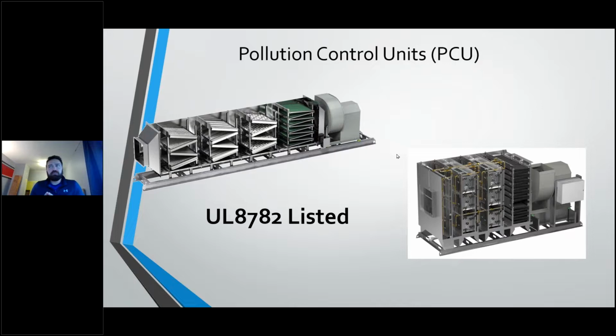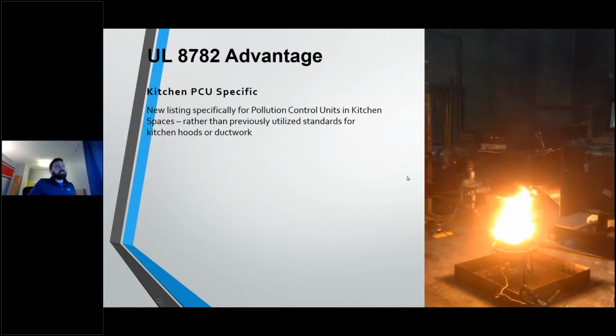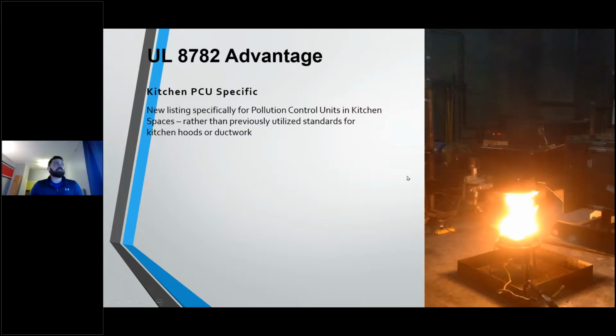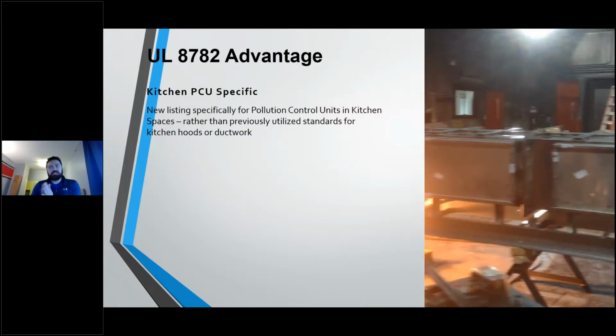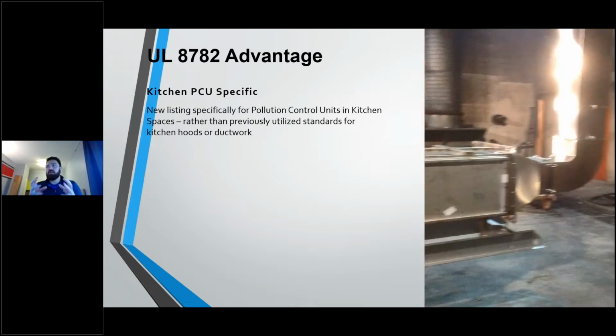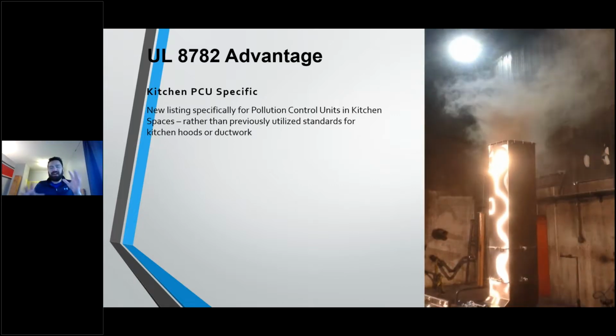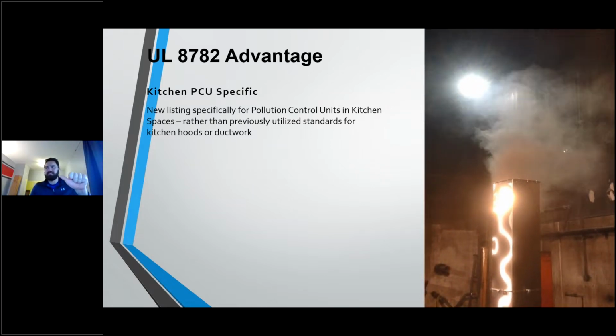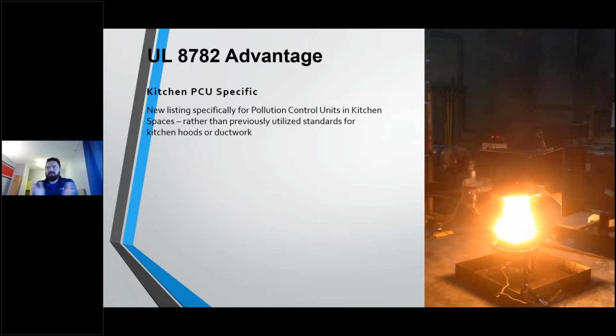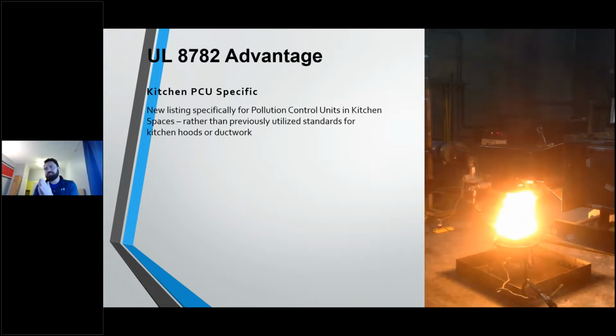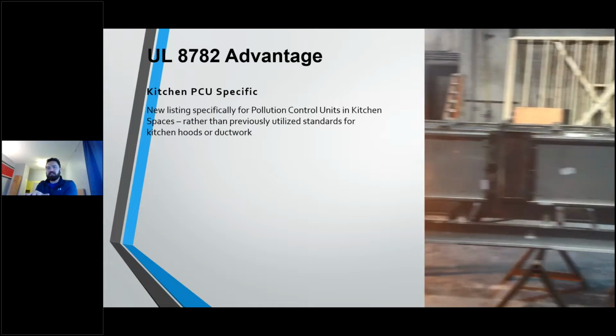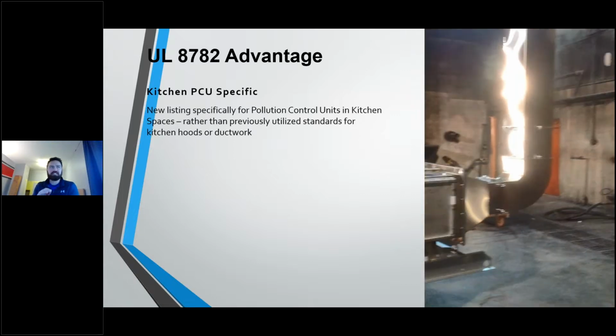The UL 8782 is the new standard in pollution control units. So what is UL 8782? It's a relatively new listing. All right, so this is a kitchen-specific PCU listing. Previously, there was no UL testing standard for pollution control units. So you had to use this weird combination of the UL 710 listing and a grease duct listing, and a pollution control unit is not really any one of those two things. So there was no consistency in the industry on how these units were being tested.